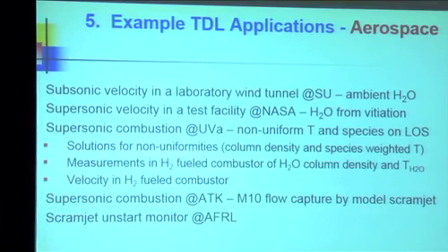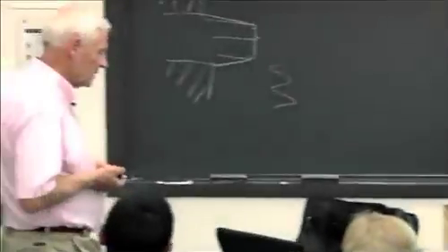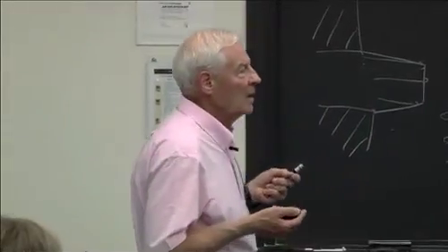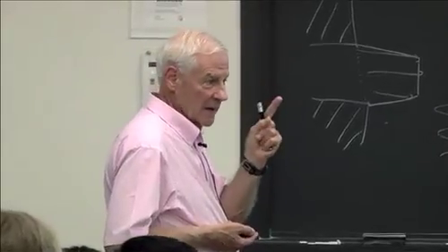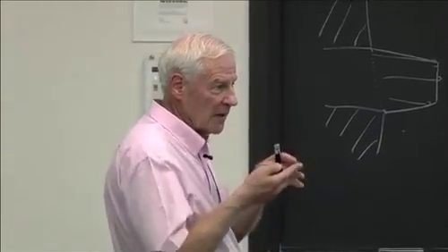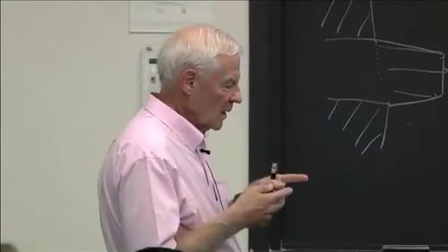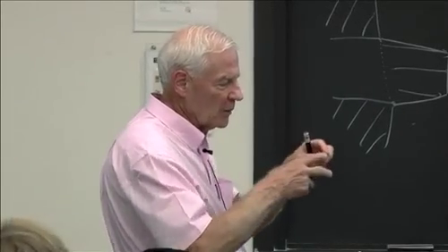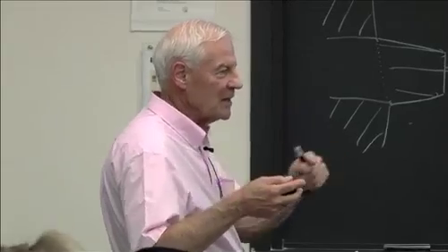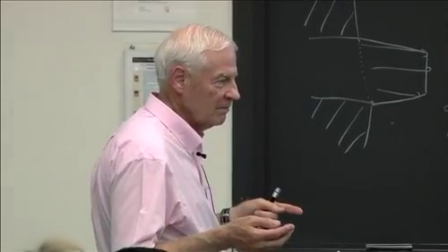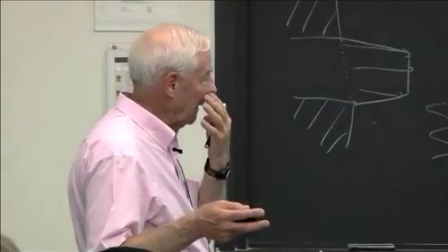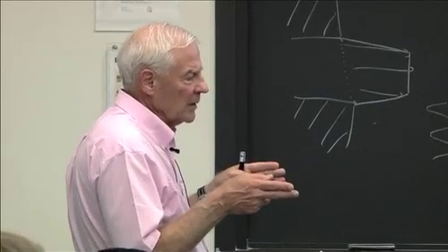You did mention a spectrometer in your detector. How do you know what wavelength you're at? Okay, so there are a couple of reasons why we don't have a spectrometer. The lasers are monochromatic, so we know that there's only one color. We don't need a spectrometer to filter out the ones we don't want. We mostly care about the change in wavelength, not the absolute wavelength. So we have a little box that's called a wave meter. We send some light into the box, and it tells us the wavelength to several significant figures. So it's not a spectrometer, it's a wave meter. That tells us the nominal wavelength.